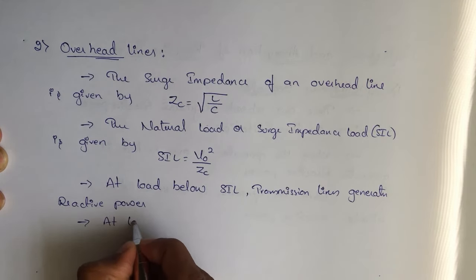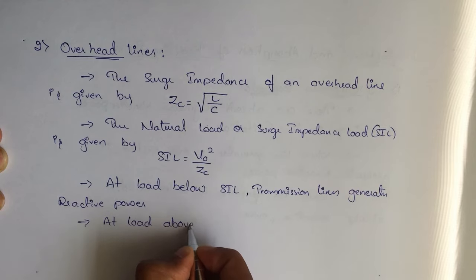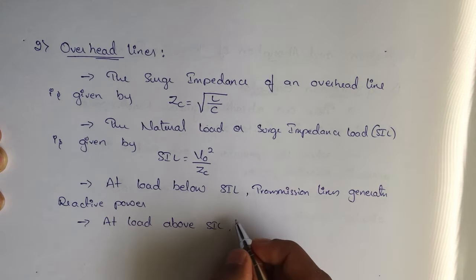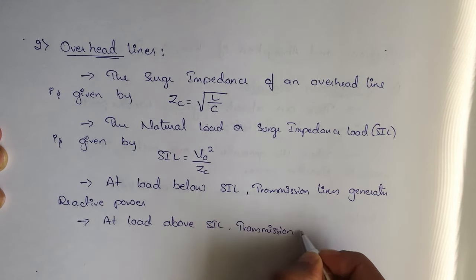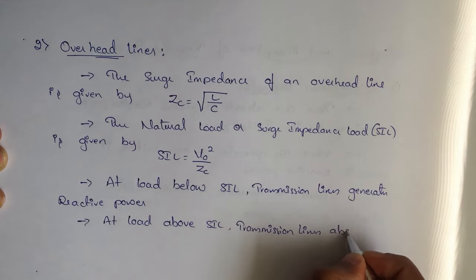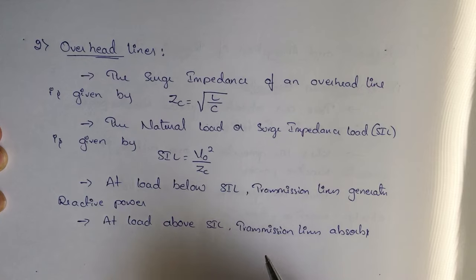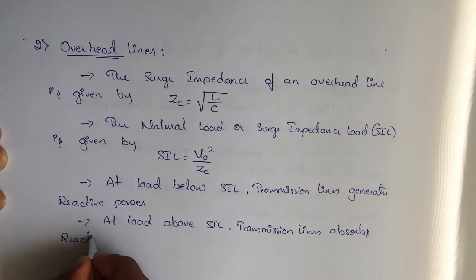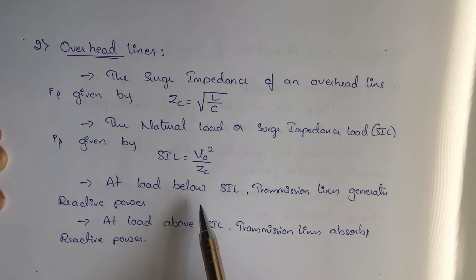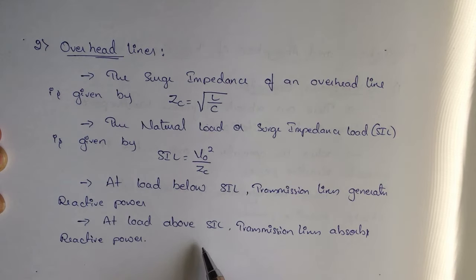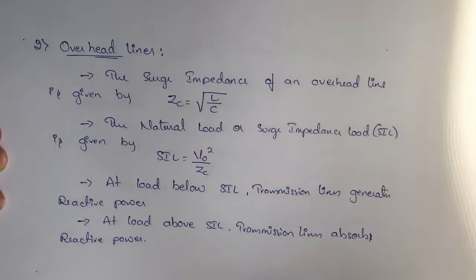If the load is below SIL, the transmission line generates reactive power. If the load is above SIL, it absorbs reactive power. So the overhead line acts both as an absorber and as a generator of reactive power.